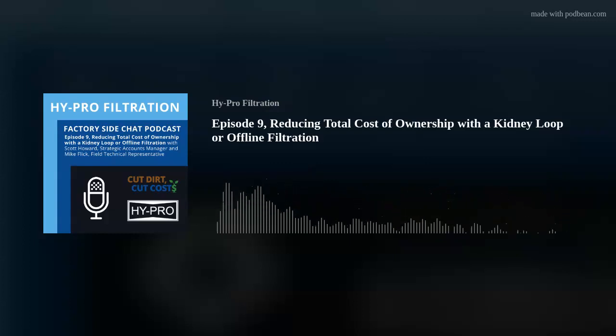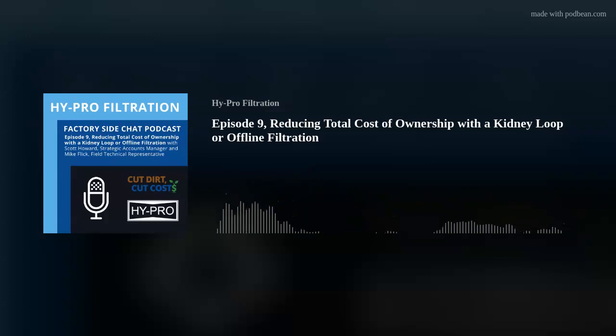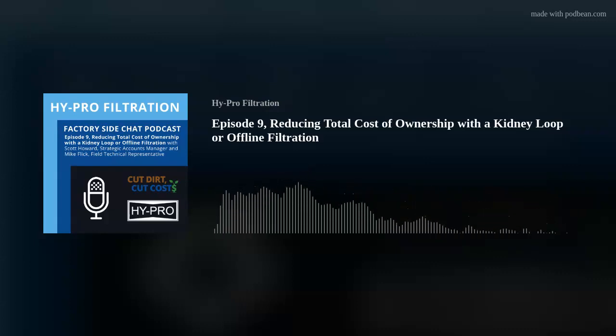We'll divide that by 24, which will give us how much oil we need to pump in an hour. And then we'll divide that by 60 to give us oil flow in gallons per minute. And that will be our kidney loop pump size. And once we have that kidney loop pump size, and we have the oil viscosity and the temperature we're going to be running at, then we can make a calculation and pick out our filter size and make sure that we have the proper pump flow to turn the tank 16 times a day, and that our clean pressure drop on our filter is 5 psi or less. This will allow us to make sure that the oil is clean, they're getting enough turns in a day, and that should be adequate to protect all their components in their system.